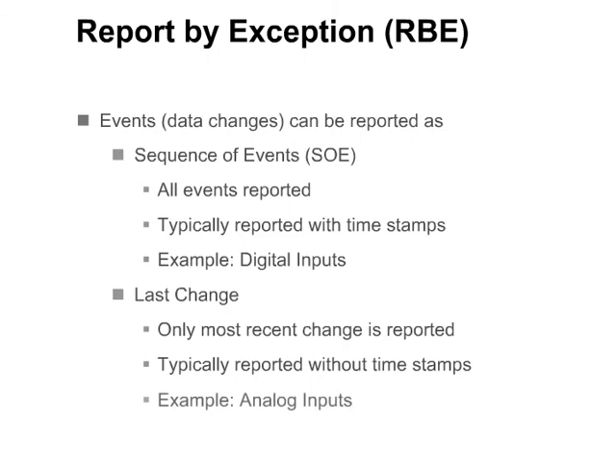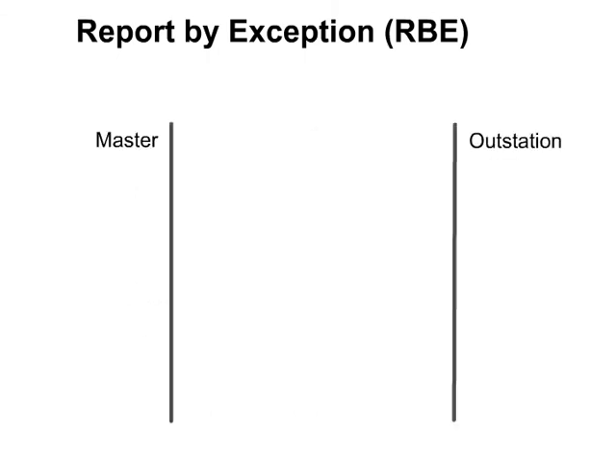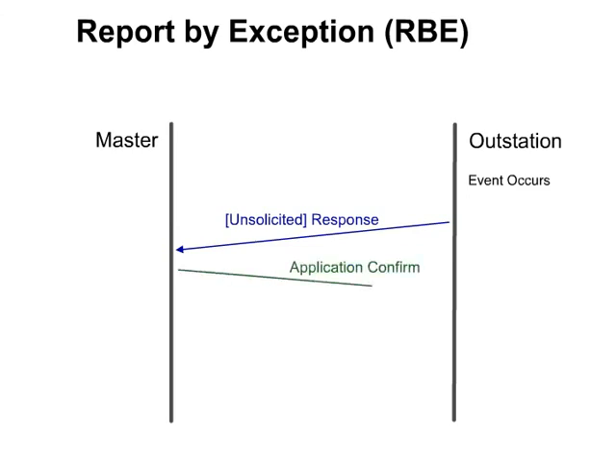Here is an illustration of reporting events via the report by exception mechanism. First, an event — for example a binary input change, or an analog change in excess of the deadband — occurs in the outstation. The outstation reports this change via a response to a class poll, or via an unsolicited response. The master confirms receipt of the events by sending an application confirm. The outstation removes the reported events from the event buffer only after it receives the application confirm from the master. This guarantees delivery of the event to the master.